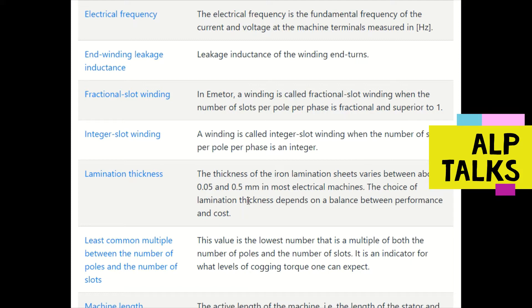Lamination thickness: all magnetic material is used in laminated sheets. The thickness of iron lamination sheets generally varies between 0.05 to 0.5 mm. The choice of lamination thickness depends on a balance between performance and cost — lower losses and better performance come at higher cost, while lower cost results in higher losses.